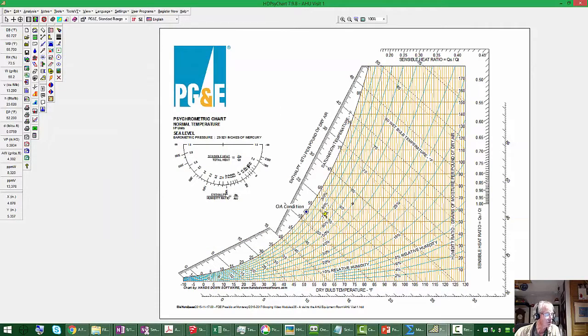And we're going to assume that the temperature in the building is basically at or around the standard this hotel has for their ballrooms, which is 72 degrees Fahrenheit. So to figure out what the outdoor air specific humidity is, there's actually a number of ways we could do that. One is, you'll notice if you watch over here, as I move this cursor around the chart, it's telling me the values under the cursor.